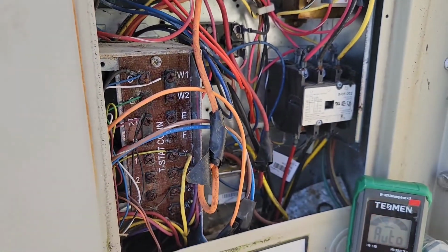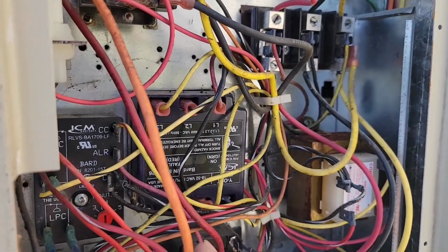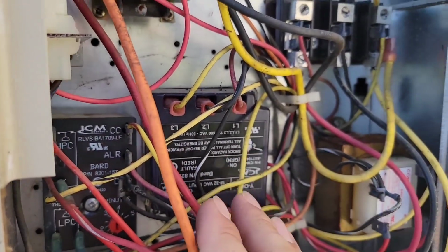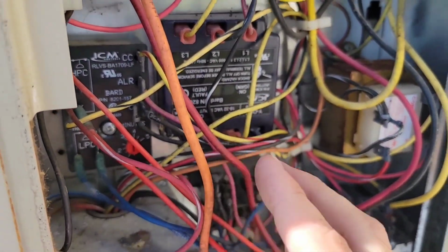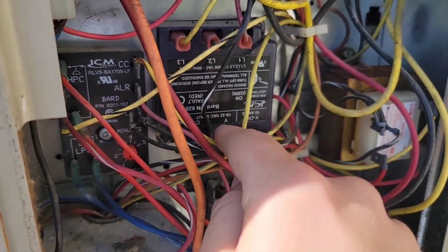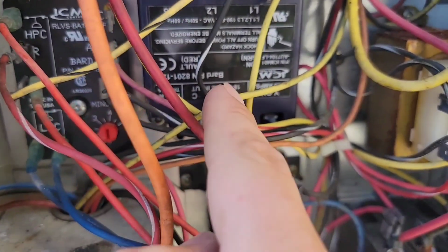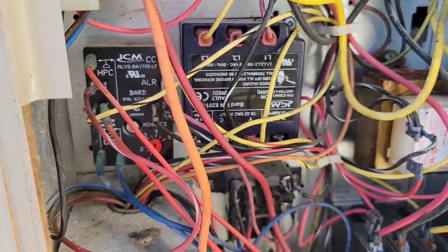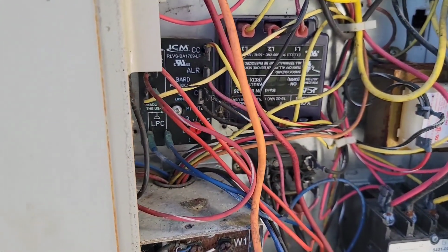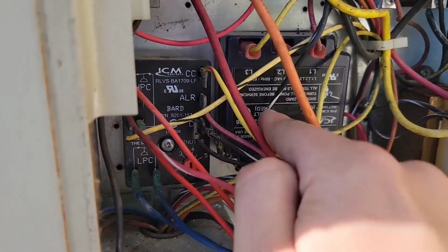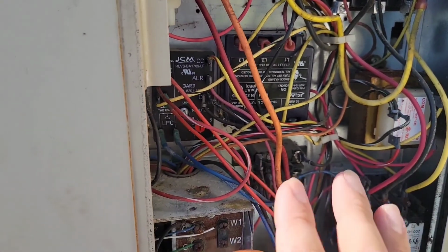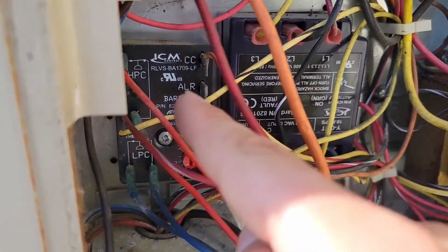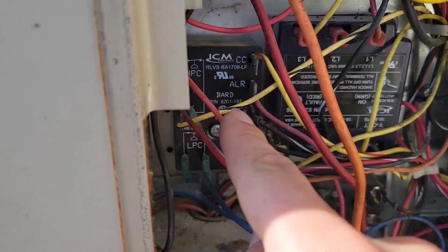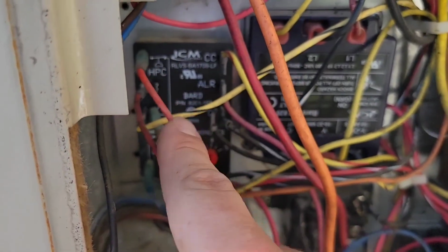So we've obviously got an issue. Maybe we had an issue and our phase monitor picked up the issue, and then it had an alert. But usually there's a red light, and there wasn't a red light, there was a green light. So we obviously reset something. We've either got an issue that's caused this, or we could have a bad phase monitor or a control problem. So this part right here.